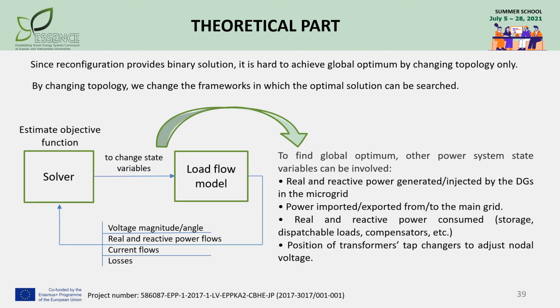Since the system variables change in time, the same topology may provide different values of objective function. In fact, to find the global extremum of objective function for a certain topology, it's necessary to adjust controlled system variables. In general case, the solution of network reconfiguration task requires a load flow model and a solver that may utilize different algorithms to find extremum of objective function. No matter which kind of algorithm is used, in general it's a search among multiple possible system states that are estimated with load flow model.